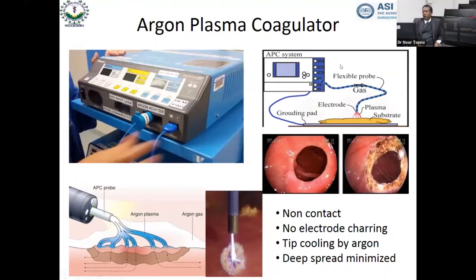Now, APC, or the argon plasma coagulator, this is basically the good thing about this. I will not go into the process of how it works, maybe in some other scenario, because that would make it too long. The most important thing is it uses argon gas, and there is creation of a plasma environment over there. And this plasma, even in the inert gas which argon is, actually conducts electricity, and therefore it's a non-contact method. There is no electrode charring, and the flow of argon, which is under high pressure, also results in cooling of the tip.